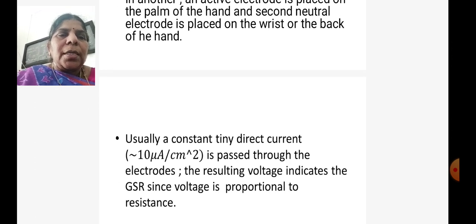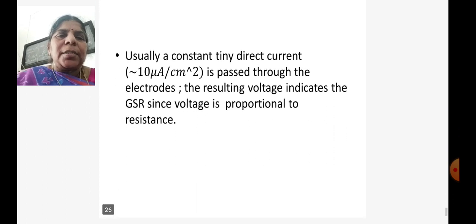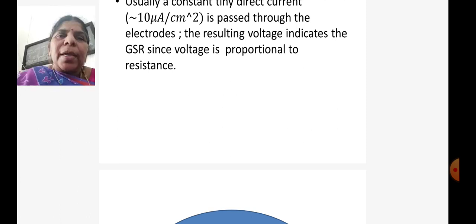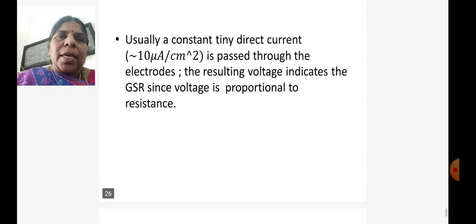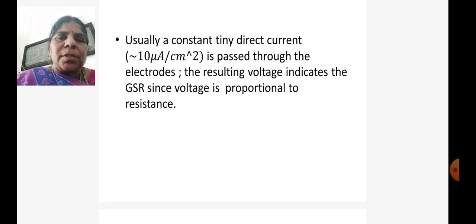Usually, a constant tiny DC current of the order of 10 microamps per centimeter squared is passed through the electrodes, which causes a resulting voltage that indicates the GSR. Since voltage is proportional to resistance, you can calculate the galvanic skin response. This GSR measurement is based on sweat gland activity. When the sweating is more, the resistance will be less.